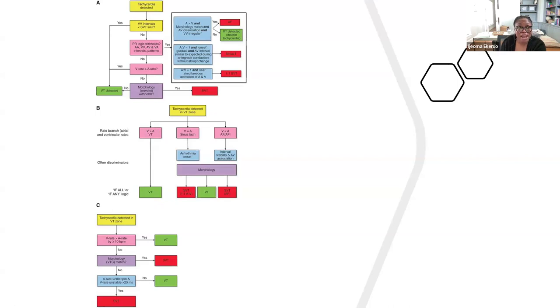Now, during times of an atrial arrhythmia, there are some times you have a change in your sensing. For instance, in sinus rhythm, your atrial sensing could be as high as 2.5. But then when the patient goes into atrial fibrillation, or maybe atrial flutter, and one of the P waves is hidden in the QRS and in a blanking period, it's not going to track it or see it, and it might read V's greater than A's and put it into the wrong bucket.